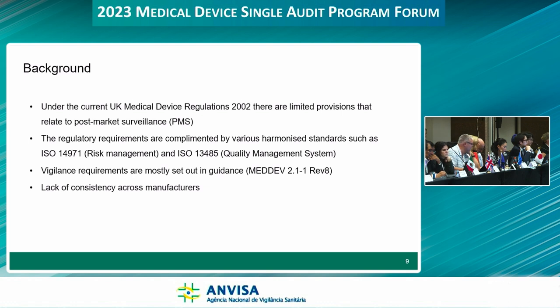The vigilance requirements that we currently use are set out in the European guidance MedDev 2.1.1 revision 8, and they're basically post-market surveillance. There's been a real lack of consistency among manufacturers as to how they handle post-market surveillance, which we think is a really important element.